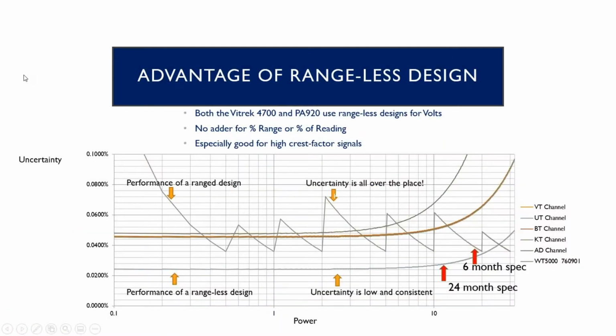I wanted to talk a little bit about the advantage of a rangeless design. We use a different approach than most other test equipment companies. This shows power across the x-axis and uncertainty across the y-axis. So when you're in the upper left corner, it means you're at real low power but high uncertainty, which is not good. What happens is most devices have an adder for percent of range or percent of reading, and this is how they perform.